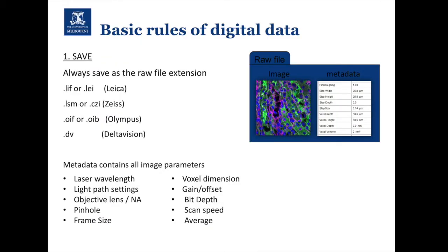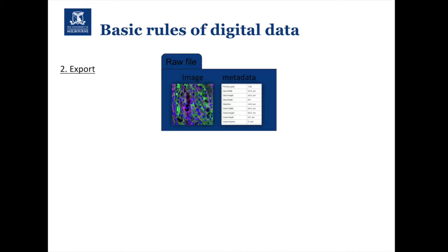Our basic rules of digital imaging: first, always save your data under the raw file extension. On a Leica system that would be .LIF or .LEI; on Zeiss it's .CZI, and so on. The reason is that this saves not just the image but also what we call metadata — information about exactly what the microscope settings were when you took that experiment. A lot of software also allows you to reuse those settings on another day, so you can be imaging in exactly the same way weeks or months apart.